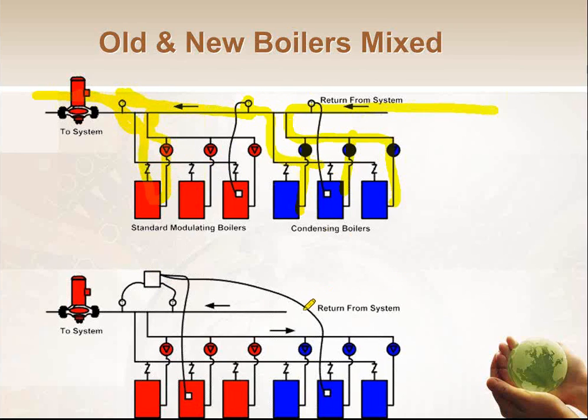Depending on the kind of control you have, you may choose to pipe it like the bottom drawing. Once again, though, the key is I've got to fire the condensing ones first. They get the chance to heat the water first with 1, 2, or 3 of them, however many it needs. If it's warm enough, great, life is good. If not, fine, kick on another one of these other old boilers on those extreme days. What you find is that you almost never need all the boilers, and when you do need a backup one, it's only for certain times a year for a certain amount of hours, and you get most of the run hours on the condensing boilers.